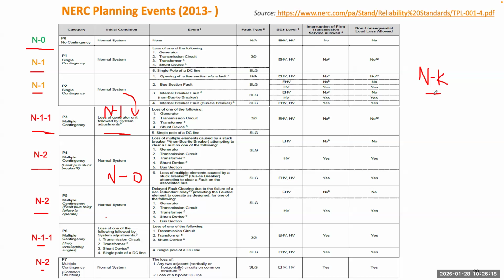If we talk about just the loss of a substation, but you can also lose a circuit, like a transmission line, or maybe a transformer. So if you also count transformers and transmission lines, the total number is now not 70,000. It could be maybe 200,000, right? There are so many elements. So even N-1 can be a huge number, right?